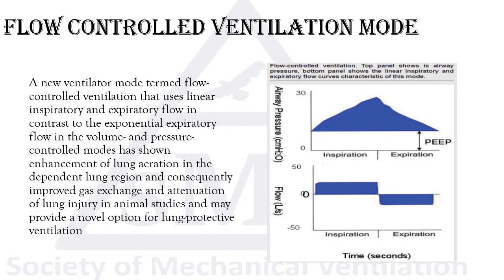Worth mentioning that there is a new ventilator mode called flow controlled ventilation mode. And that's unique. I have never seen it, and it's only on one ventilator. It basically uses a linear inspiratory and expiratory flow, as you can see here, a constant inspiratory flow.